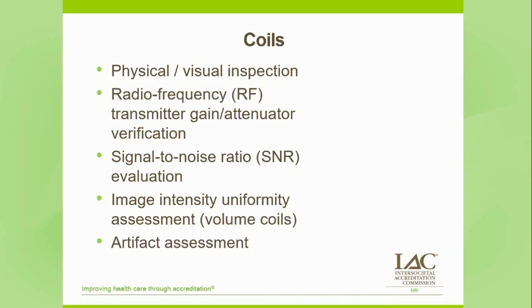Your signal-to-noise ratio is measured from the images themselves, making it a true end-to-end test of the coil. It's hooked up to the system, runs the same imaging sequence each time, and this measurement will tell you whether the coil is collecting the expected amount of signal and the expected amount of noise. These values should be consistent over time and fall within a specification to tell you whether the test passed or failed.